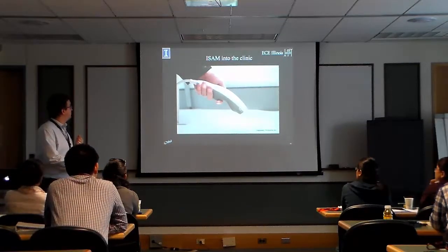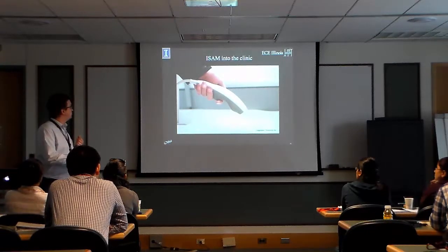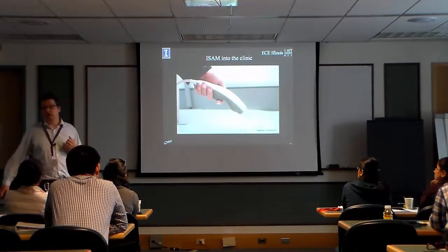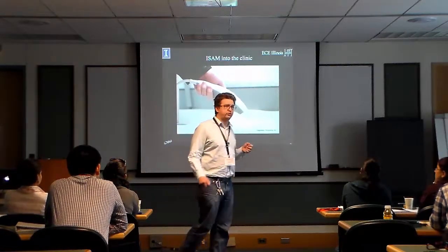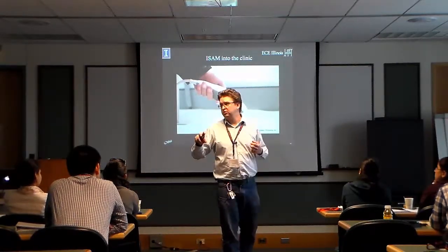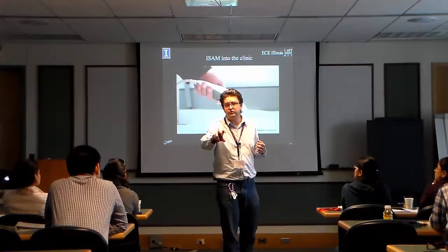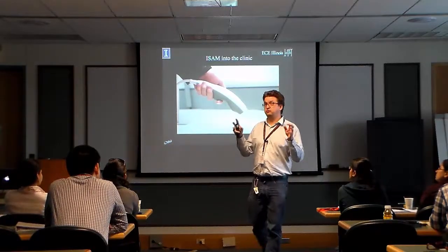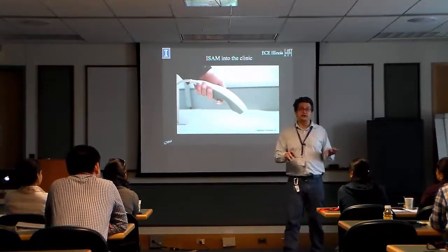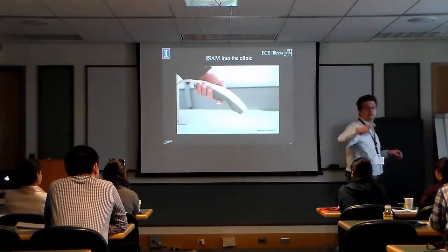And this is now a high-resolution OCT machine packaged in a fairly small handheld wand. And it's small because you no longer have to worry about refocusing through the sample. You just leave the focus fixed, and that lets you build in fixed optics and lets you build things small and compact and robust.